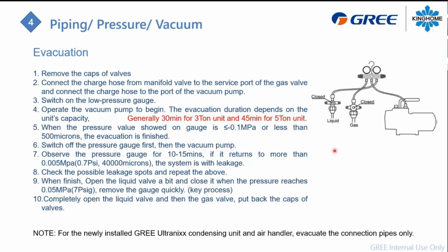So make sure you do two different vacuums, one for each line, because you do the vacuum only in your line, so it won't take you a long time to make it a good vacuum. Make sure you attach your micron gauge. You will reach your 500 microns. Hold it for 15 minutes.